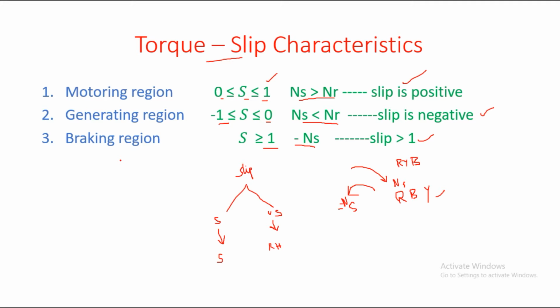In the braking region we have two types of braking. One is mechanical braking and another one is electrical braking, and here we cannot go with mechanical braking directly, because if we use mechanical braking directly, sometimes the motor will not stop. It means it is not going to obey the braking, or sometimes it is going to produce or dissipate extra heat, which will damage the machine. So to avoid that, we use electrical braking first, up to some particular extent, and then we apply mechanical braking.